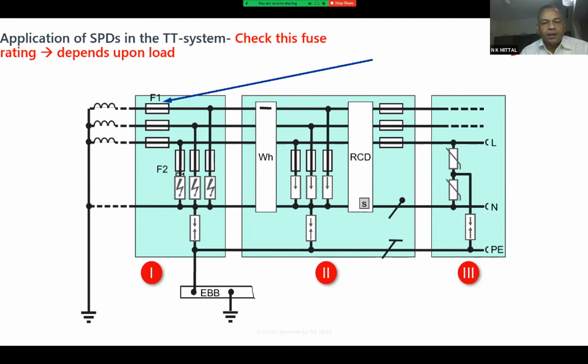That is one. Now the second distribution point, the first point may have this as type 1 or type 1+2. The second point of distribution, should it be only type 2? And what is the permissible distance, or what is the experience distance, within which, since we are using mostly armored cables, we can still go ahead with type 2, or we need not have an SPD at all? What is that permissible distance between the first distribution point or the entry point to the next distribution point? That's all.